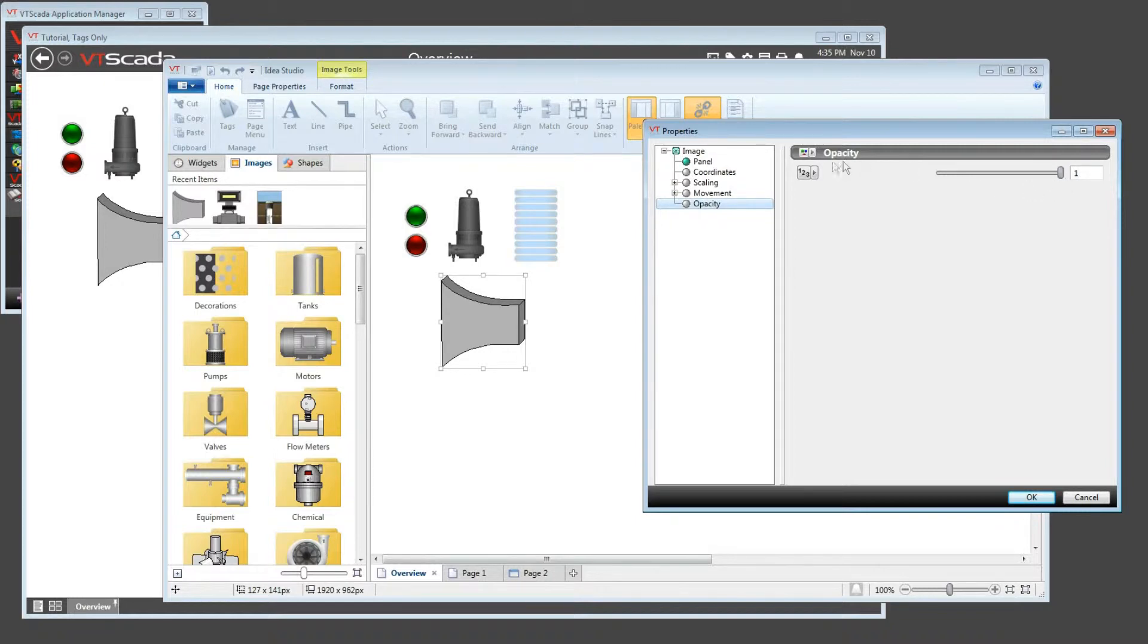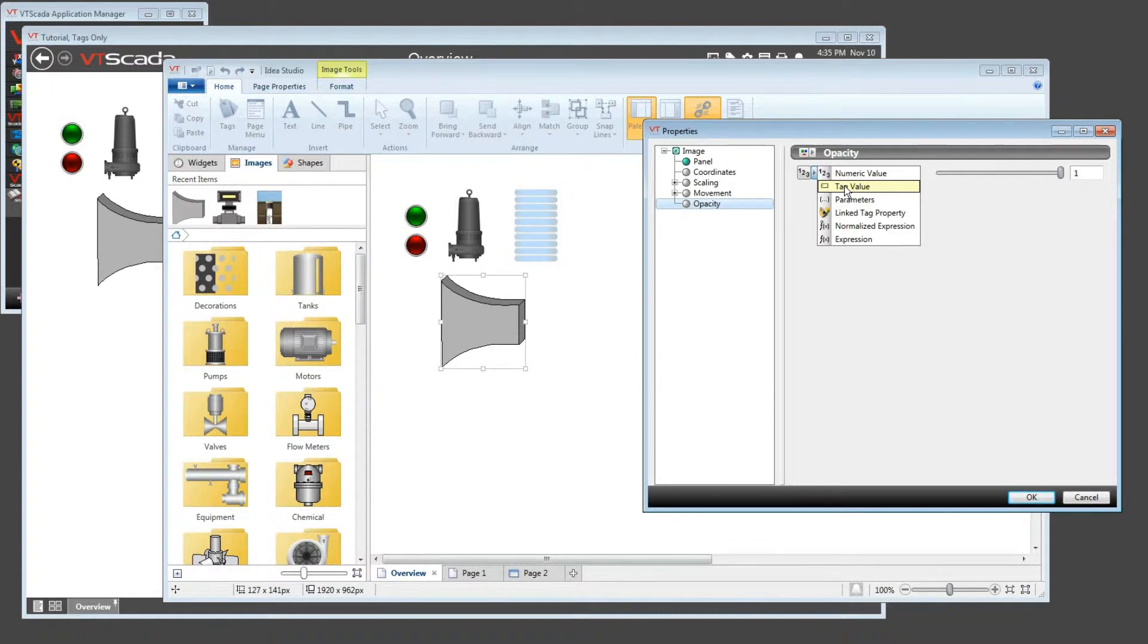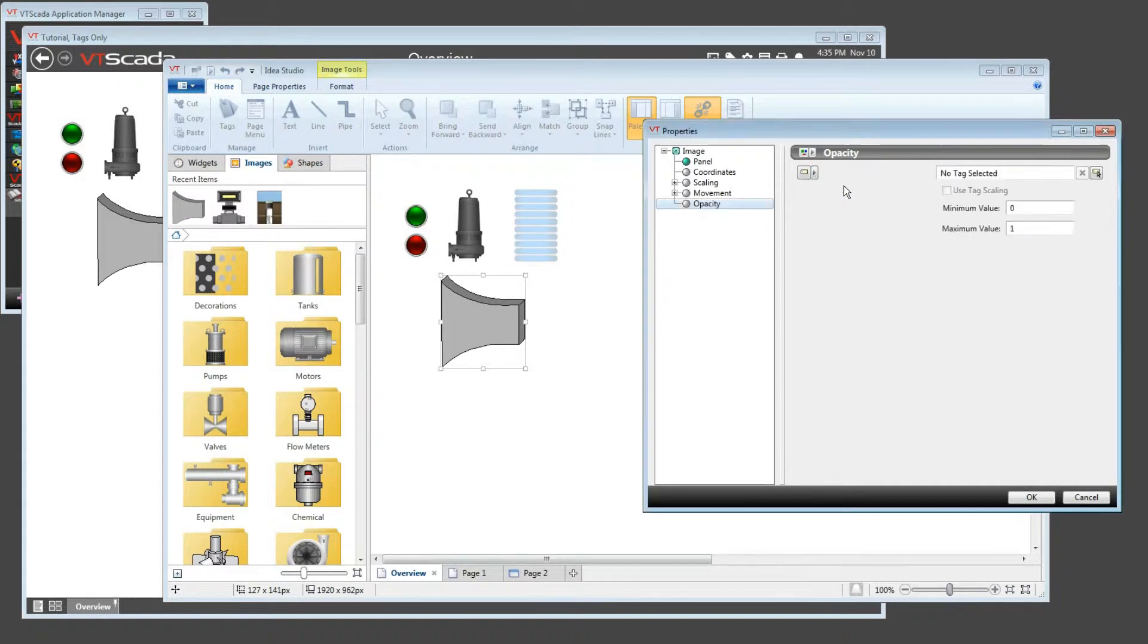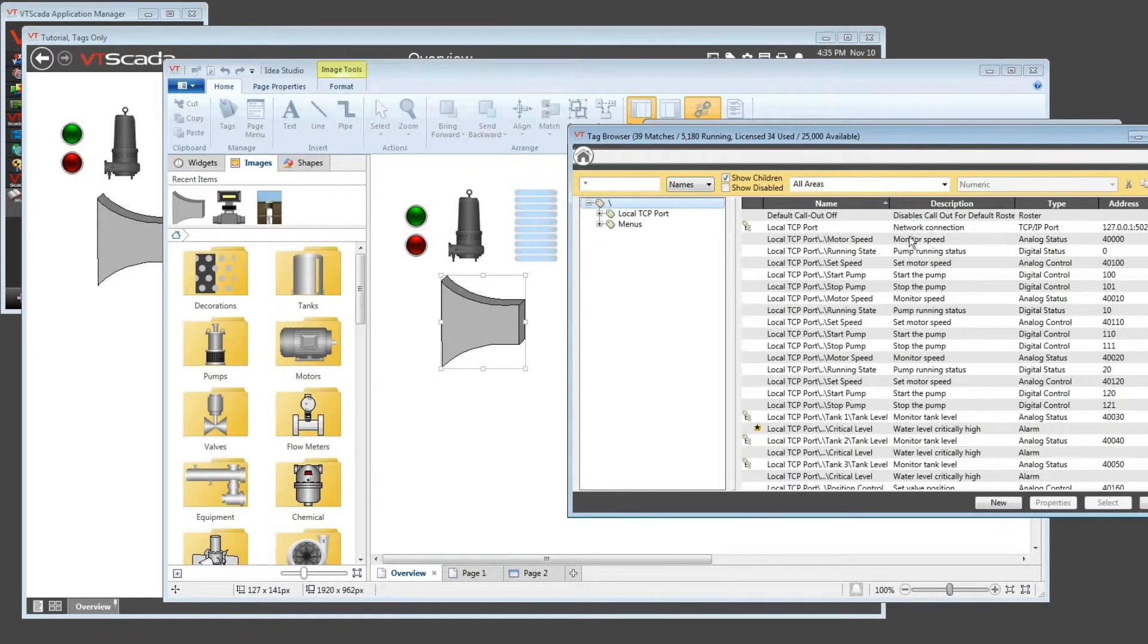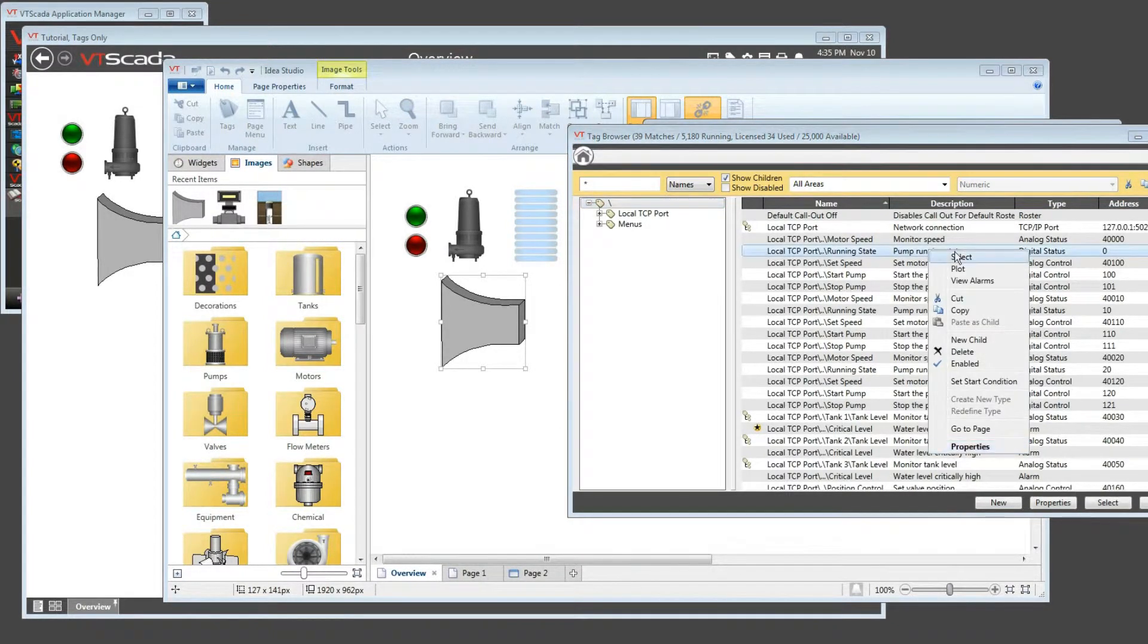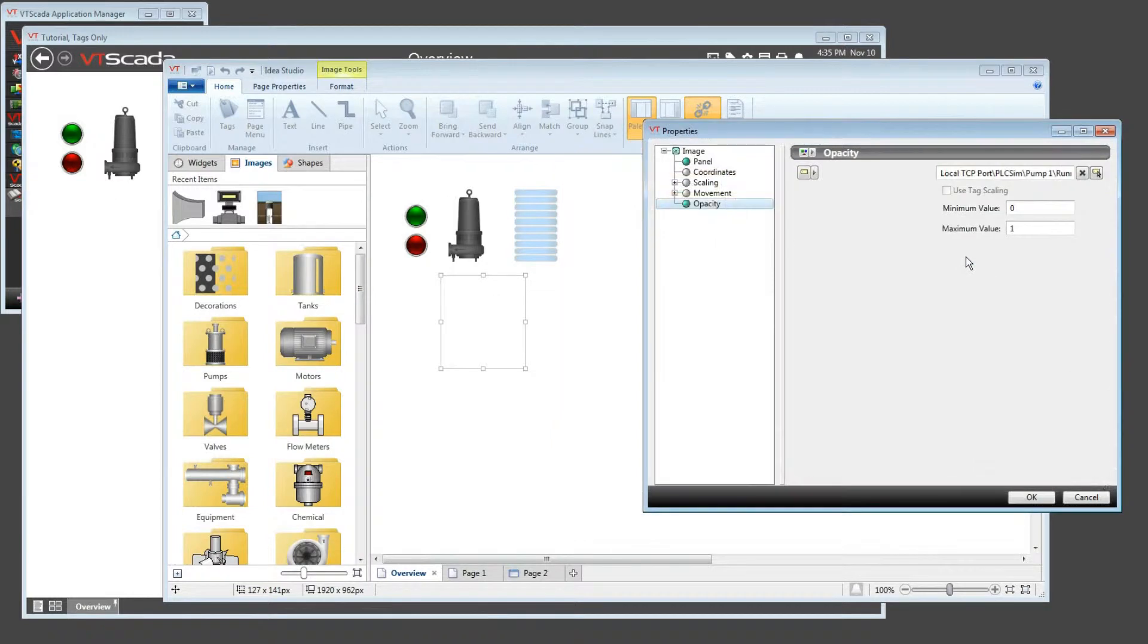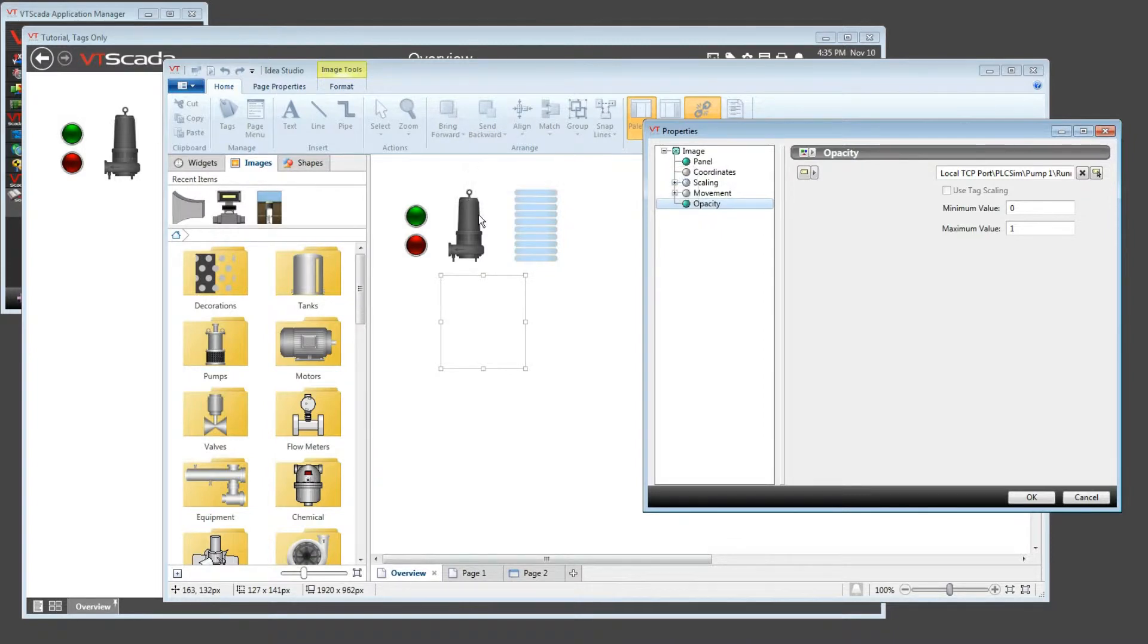Now, if instead of using a simple number, if I use this selection to find a tag, I could tie that image, tie its opacity, to any tag that I want, and I'm going to choose one that simply runs between zero or one, so the pump running status. The pump is not currently running, therefore the value of the tag is zero, and therefore the opacity dropped to zero, and the image vanished.